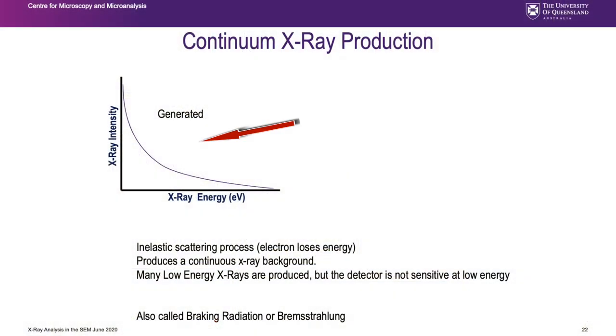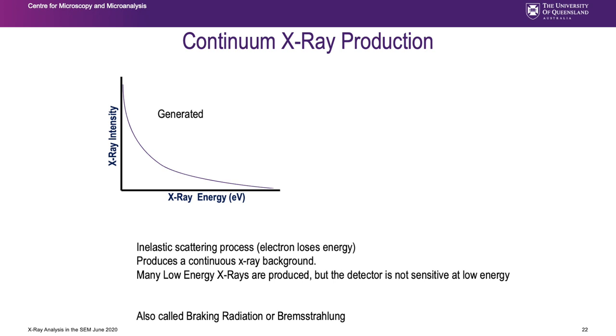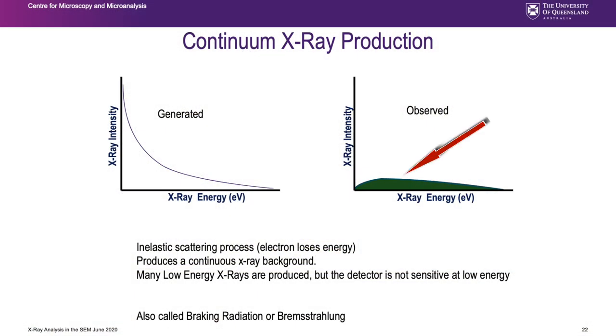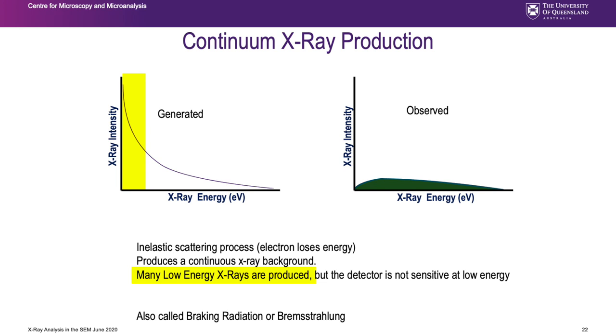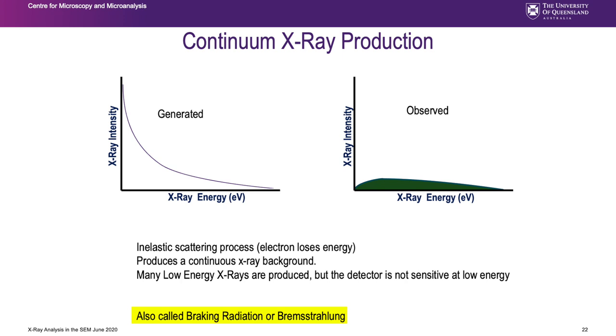The actual continuum spectrum generated looks like the one on the left - we get a large number of very low energy X-rays close to zero energy, because the most likely interaction is for the electron to lose just a small amount of energy. But we only see what our detector shows us. The observed spectrum looks different because the X-ray detector loses efficiency as it approaches zero energy. In theory the spectrum goes up towards zero, but in reality what we see falls down towards zero - that's a measure of detector inefficiency. This continuum X-ray is also called Bremsstrahlung, a common term in the literature.